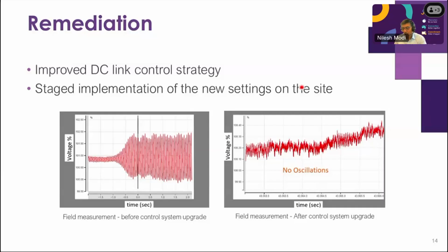Then we went to the field, implemented those settings on those inverters, and waited for the irradiance change to see whether we could see a clear onset of any oscillation in that part of the network. The one on the left side is a field measurement before the control system upgrade was put in place. There were a number of instances where we could see this kind of oscillation. Once the control system was in place, there isn't any presence of those oscillations in that part of the network. So that's a brief of investigating the 17 hertz oscillation in the West Murray area, and how we managed to replicate it through EMT modeling, and working with market participants and the OEM, managed to get an improved control system on the ground, which has helped to reduce the oscillation in that part of the network.